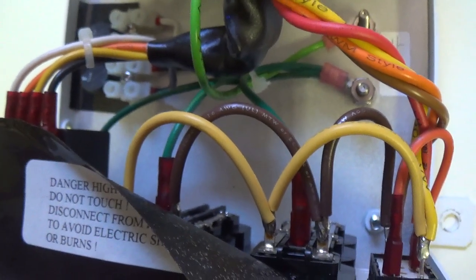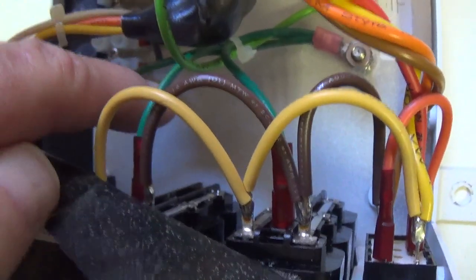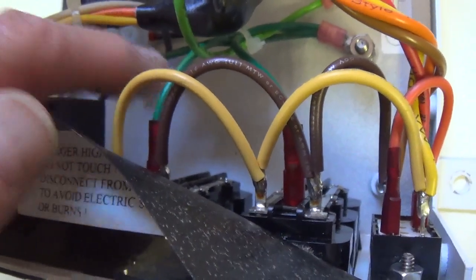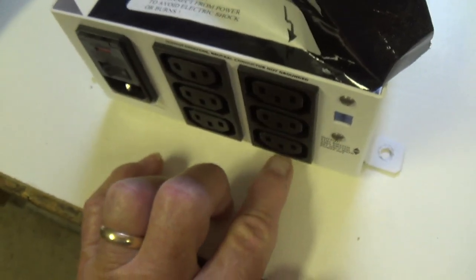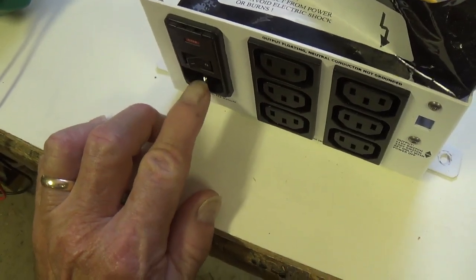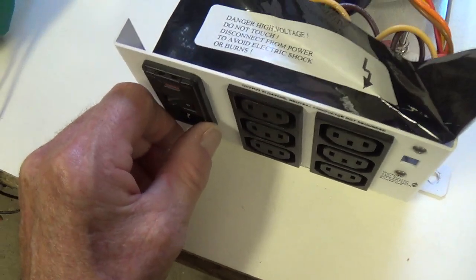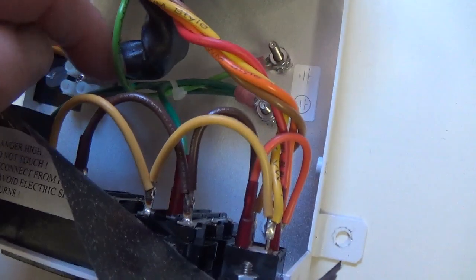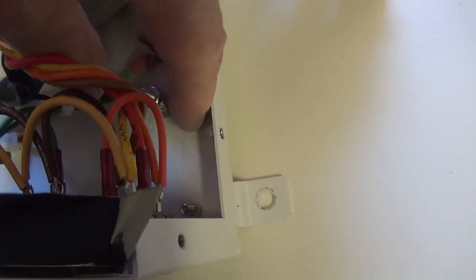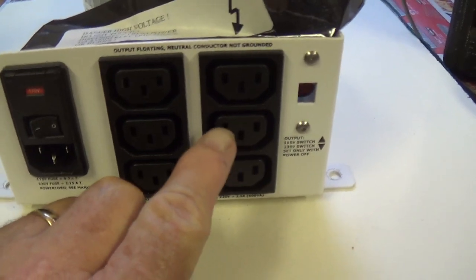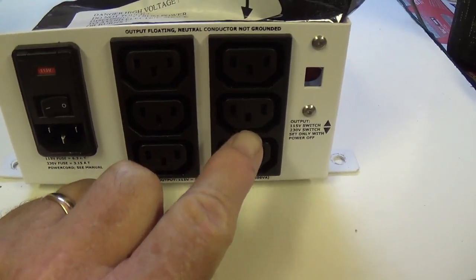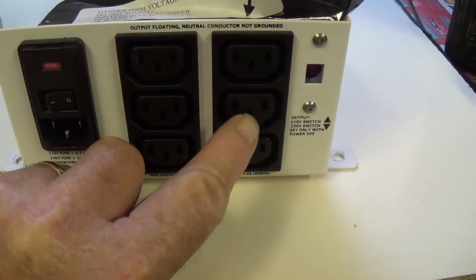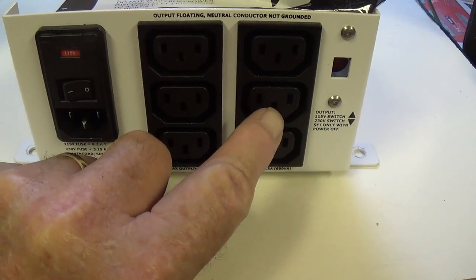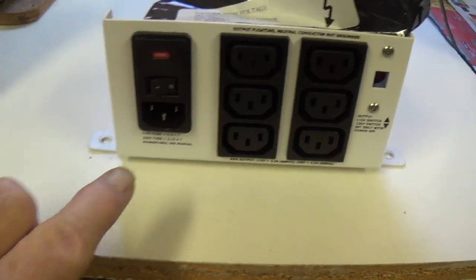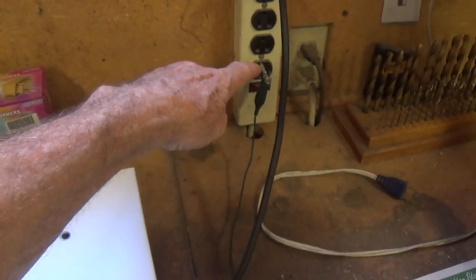The second characteristic which must be discussed is, if you look in here, there are 3 dark green grounding lines, and green is the normal color for grounds. There's one for each bank of output receptacles, and there's one from the grounding lug down here on the power cord that we're going to plug in to a wall receptacle. Now all 3 of those are combined right down here and bolted to the chassis of this unit. What this means is, when you plug in your amplifier or whatever you want to test to this outlet, you're going to get a ground reference to the chassis of that amplifier from this bottom lug, which is continuous with this bottom lug, which goes directly to the grounding lug in your wall socket.